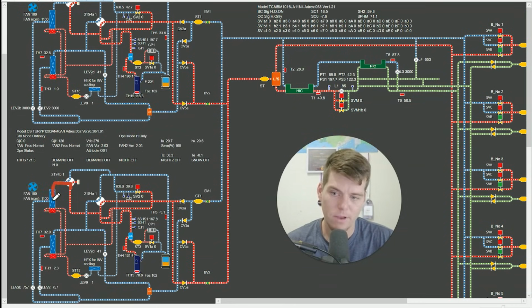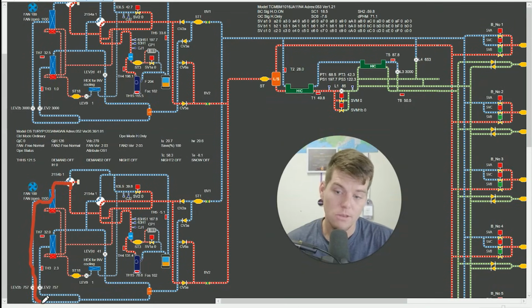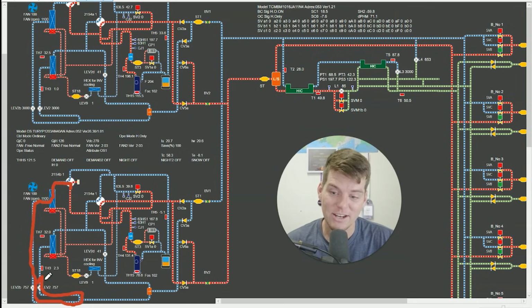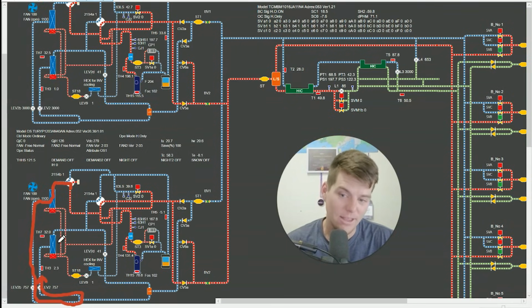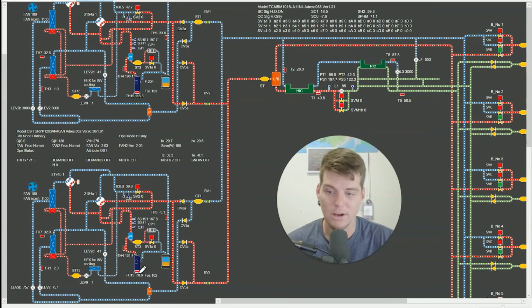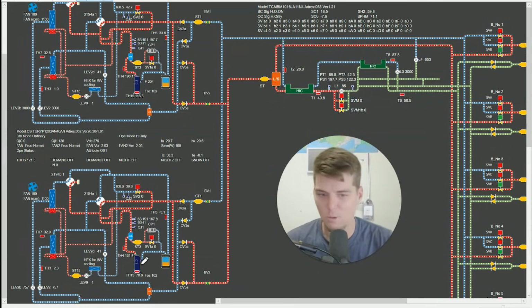Well, if this four-way valve fails, it's going to what? It's going to go through the lower heat exchanger. It's going to go back around again through the expansion valve. It's going to go back this way, and it's going to go through the metering device, back through the heat exchanger into a vapor, back over to the actual accumulator, back to the compressor. Why is that important to understand?